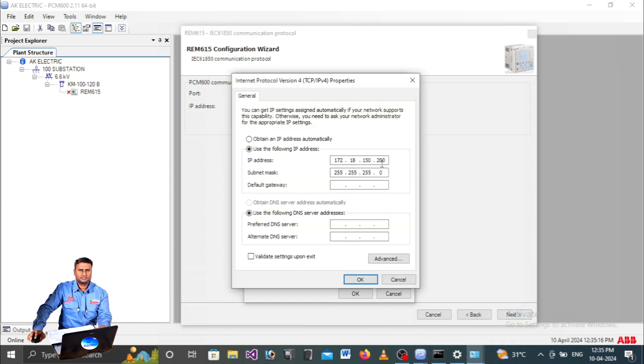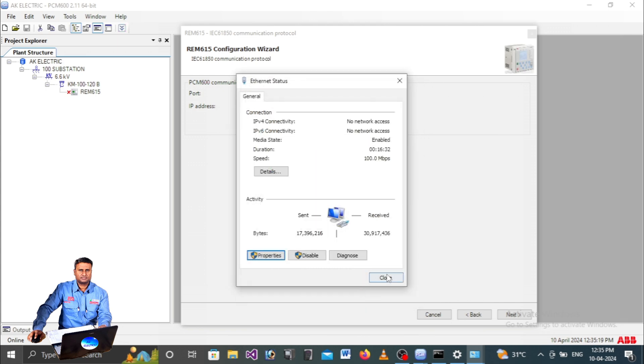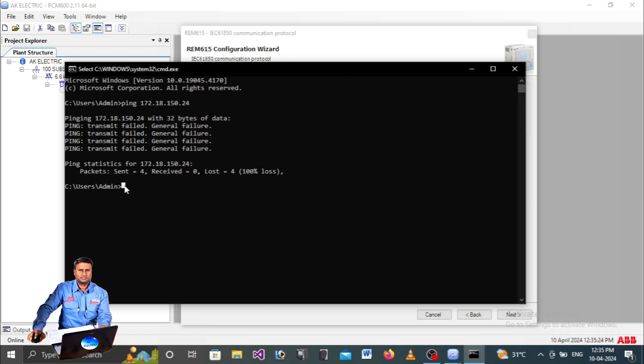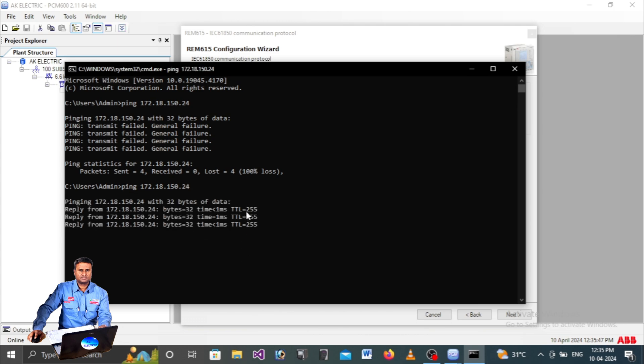Set the laptop IP address higher - for example 200 - while the relay IP address remains 24. Close everything after making this change. Then test communication again by typing 'ping 172.18.150.24' in the command prompt and pressing Enter.